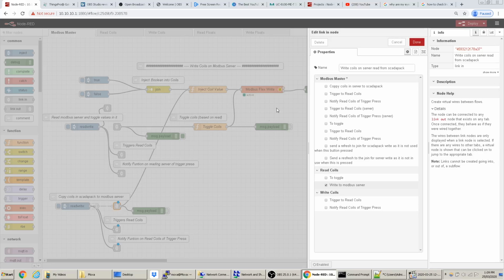It's going to write to the server. So it's not toggling anything. What it's doing is it's reading the coils in the Scadapack, and it's copying those values into the Modbus server.